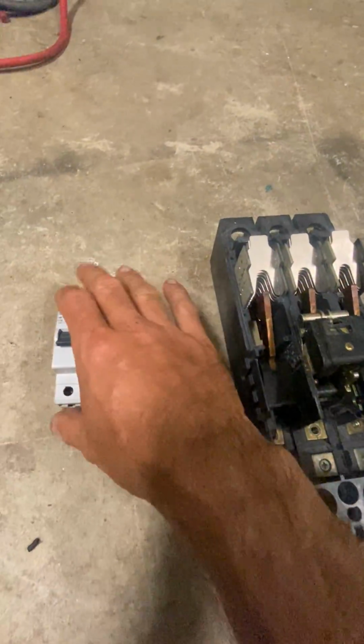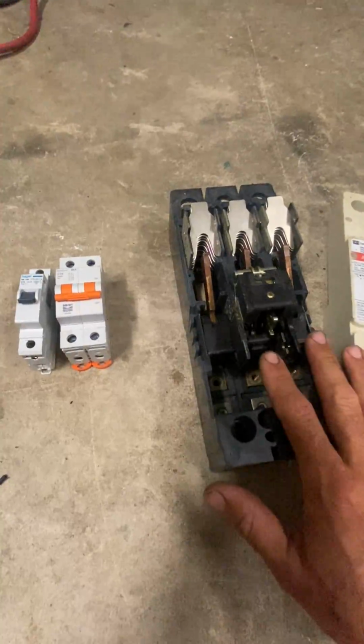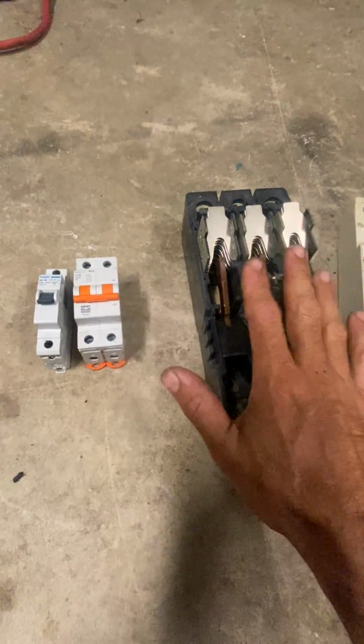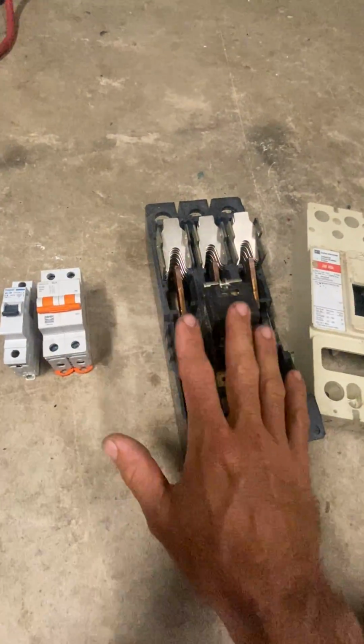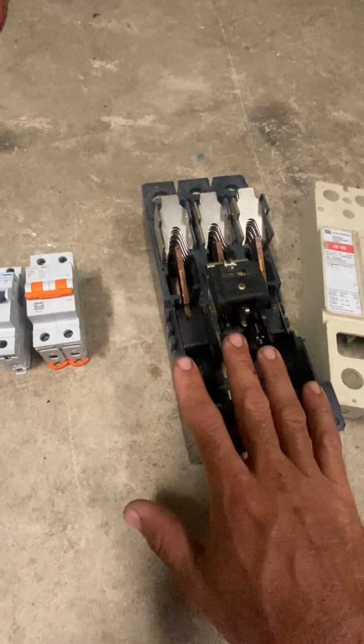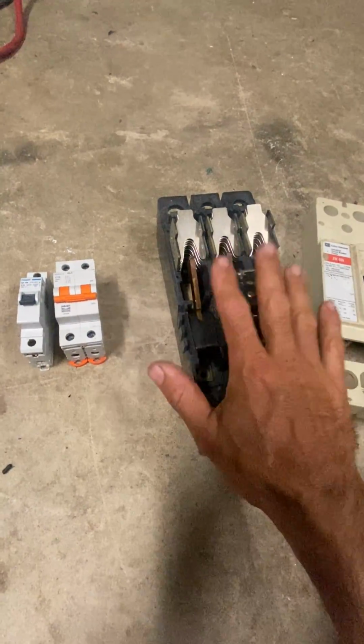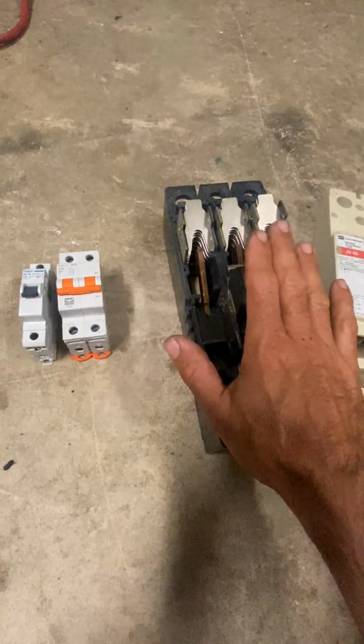So if you take anything away from this video, AC and DC are totally different, and you're going to make sure that if you're using any of this switchgear for DC, it is rated for what you want to use it for. That way, if it has a fault, it does what it's supposed to do and it trips under a fault condition.